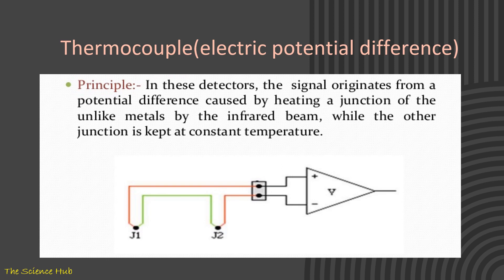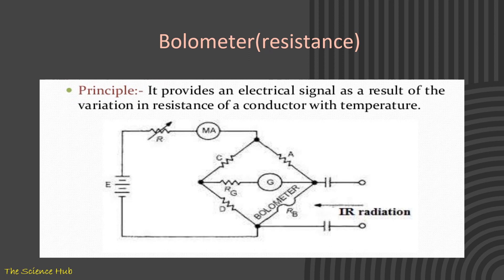Thermocouple principle: in this detector, the signal originates from a potential difference caused by heating a junction of unlike metals by the infrared beam, while the other junction is kept at constant temperature. Next is bolometer—it provides an electrical signal as a result of variation in resistance of a conductor with temperature.